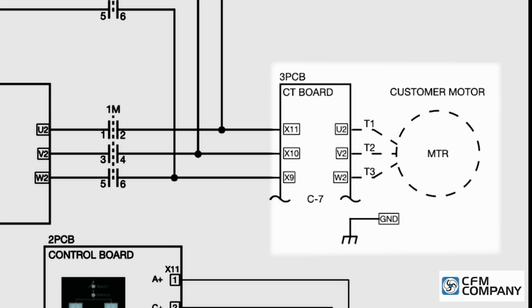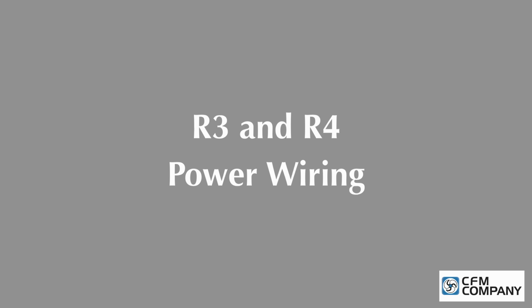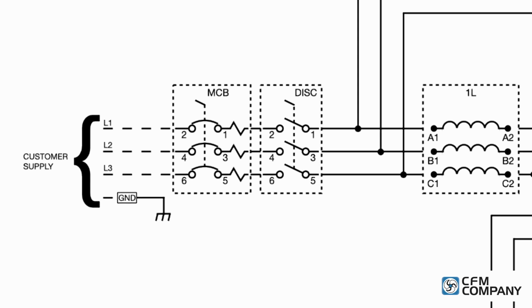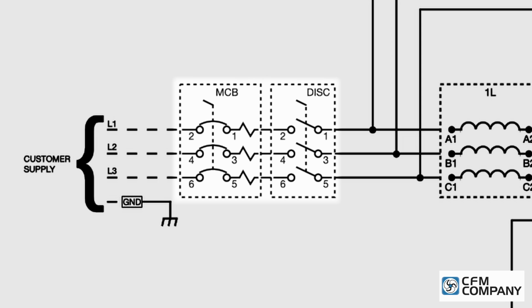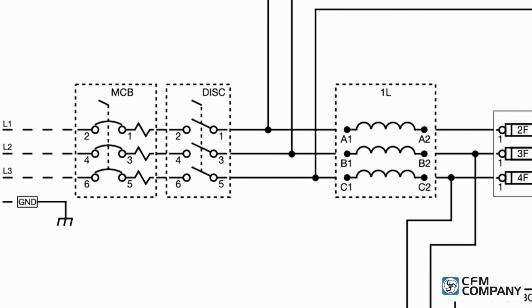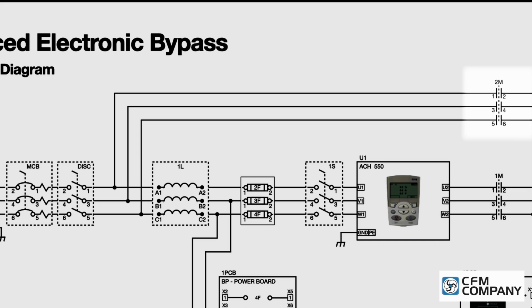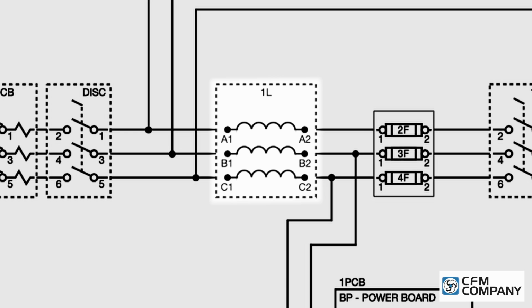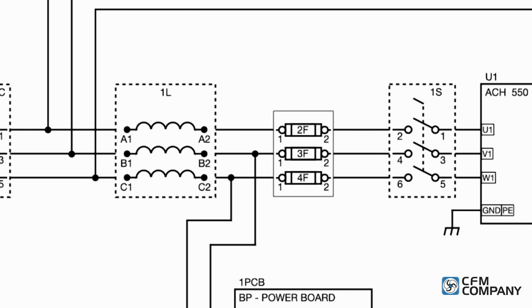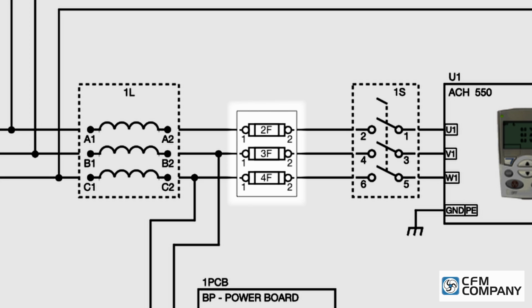The customer connects the motor leads to the motor terminals on the CT board. On frame sizes R3 and R4, the three-phase power is connected to either a main circuit breaker or a main disconnect. The power wiring goes to the line side of the bypass contactor, 2M. If equipped, the drive may have a line reactor. Next, the power wires connect to the fuse block.